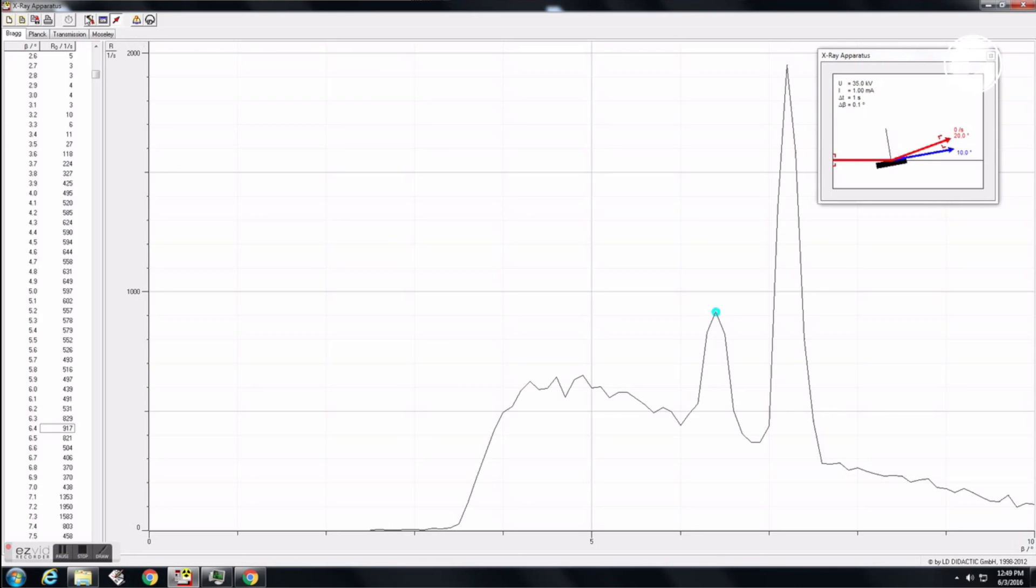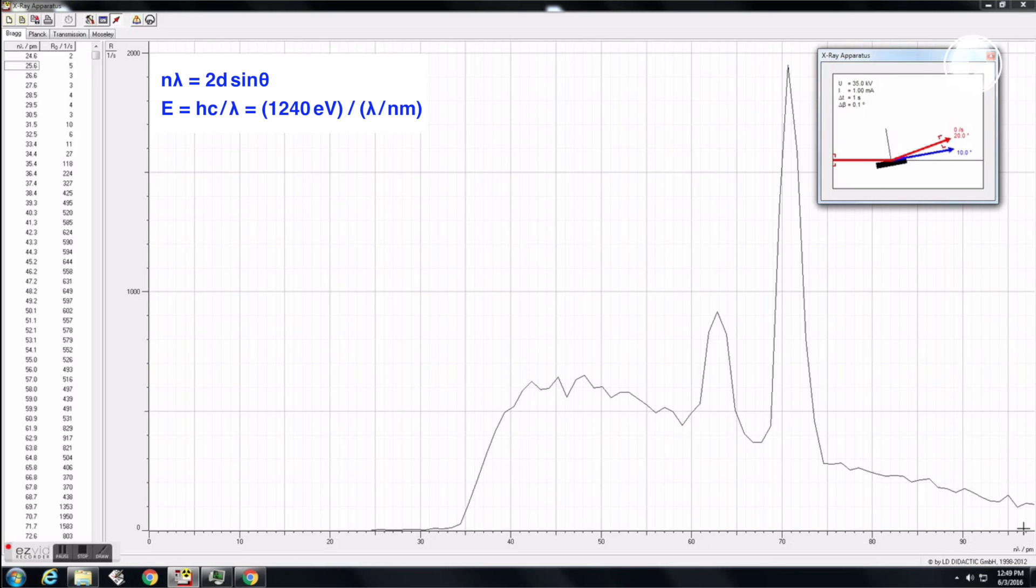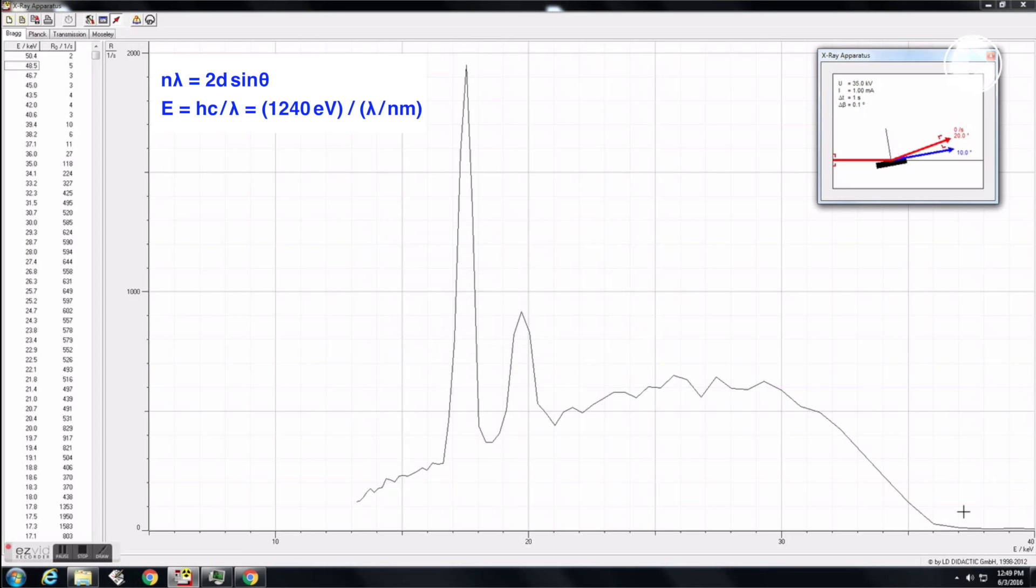Scan data should show up on the X-ray apparatus graphics display. To show the wavelength spectrum, open the settings box by clicking on the toolkit icon. Then select the correct lattice constant for the crystal. To show the energy spectrum, simply select molybdenum anode from the energy conversion drop down menu. The conversion between the angle and the wavelength, and the conversion between the wavelength and the energy, are shown on the top left of the graph.